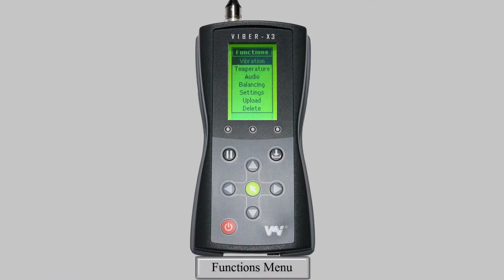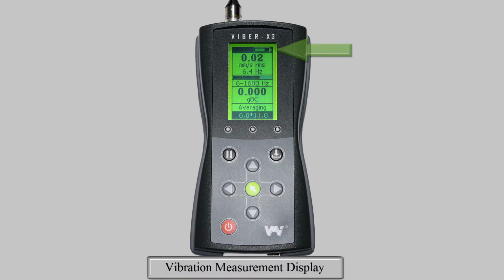Now that you're able to set up the Viber X3 to your required settings, I'm going to quickly show you how to take a measurement using each function. To take a vibration measurement, select Vibration in the Functions menu. On the digital display in the top right corner, you will see the battery meter. Below this is the vibration measurement window. It displays a reading in the chosen unit, which is defaulted to millimeters per second RMS, and a measurement of the highest peak frequency or machine speed.